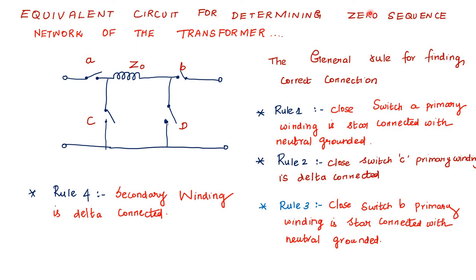I am going to explain the equivalent circuit for determining the zero sequence network of the transformer. This is the equivalent circuit which is used for determining the zero sequence current. Here A and B are meant for star connection and C and D are meant for delta connection. A and B represent star connection with grounded neutral, and C and D are closed when delta connection is present.